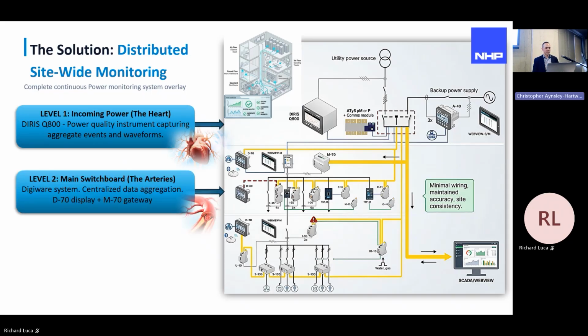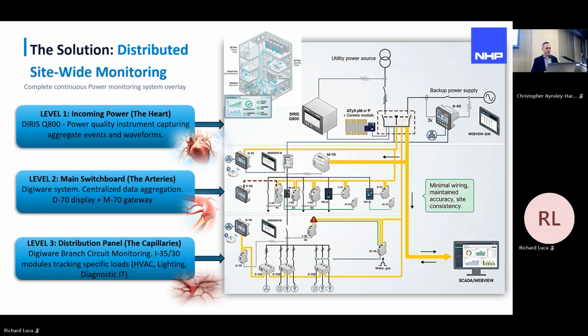So from there, we look at the arteries, the outgoing feeders. We're putting modules beside the circuit breakers, so now we can have virtual monitoring. This system can actually pick up the circuit breaker status without tying into the auxiliaries. Then the distribution panels, which are the capillaries. This is a branch circuit monitoring system. We're tracking specific loads here, HVAC, lighting, diagnostics, IT, and we're seeing everything from a fine load perspective. We can also get water, gas, temperature, any of the field devices we can put on the network too. All this is RJ45, plug and play. Back to a web server, we can view it on the web server, or back to your central head-end system.